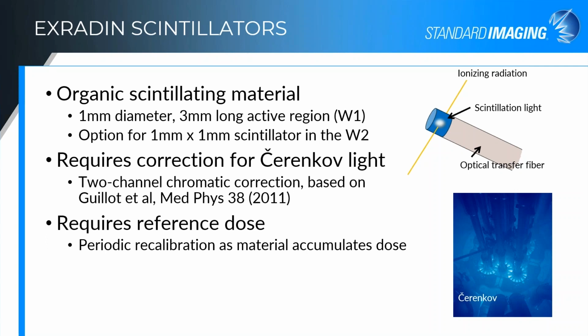The tricky part about scintillation detectors, and the reason that although they've been used in research for a long time, it's only been with the advent of the W1 that these have been available commercially for dosimetric measurements, is that you do have to correct for the Cherenkov light that is produced within that optical transfer fiber. This is additional visible light that acts like a stem effect. The more of the fiber that's in the field, the more Cherenkov that you get.